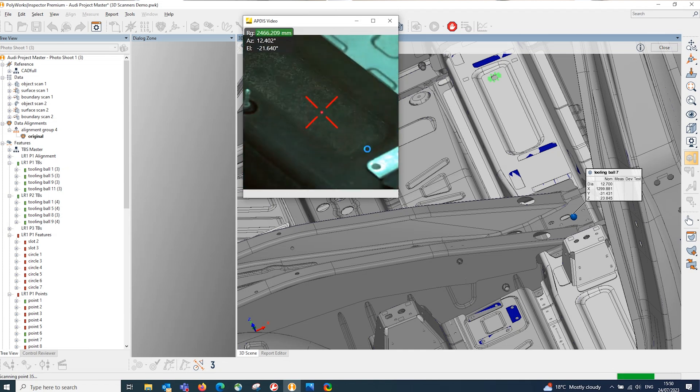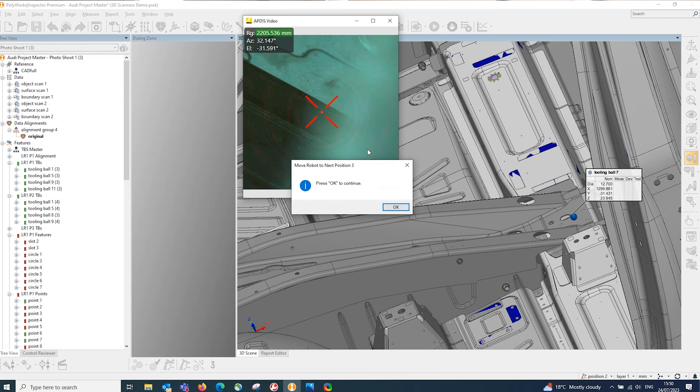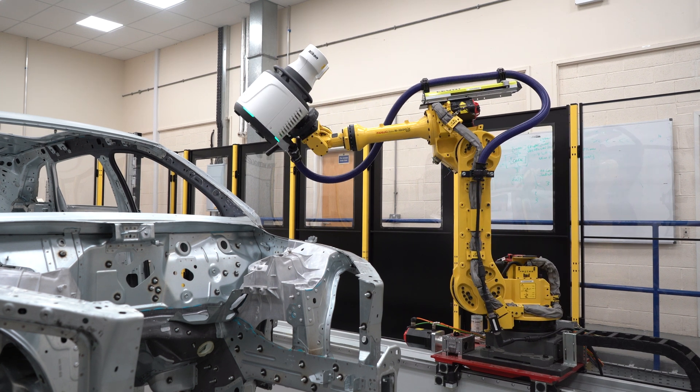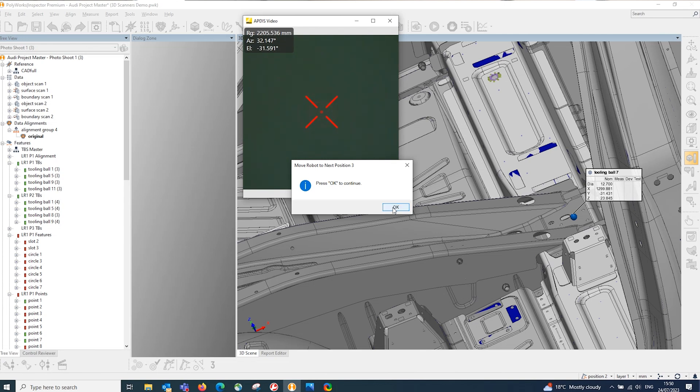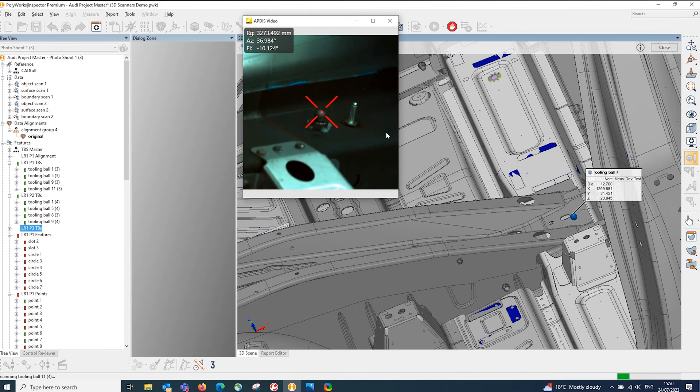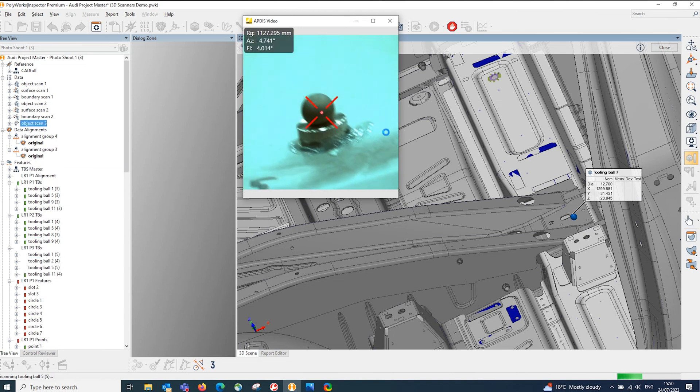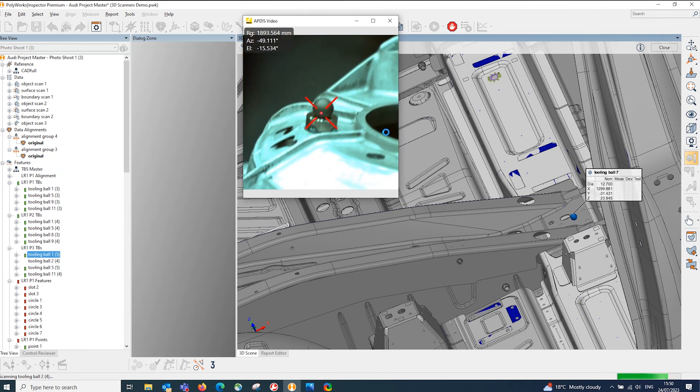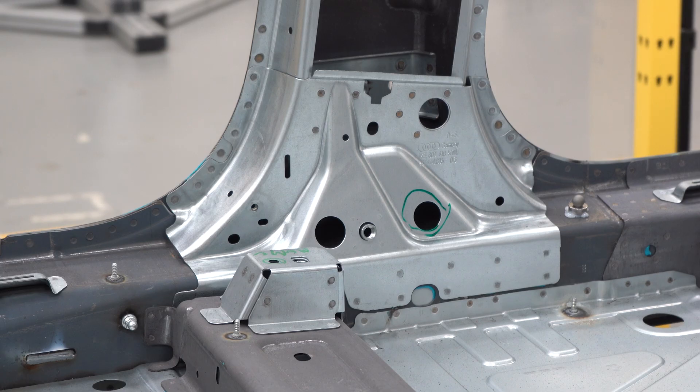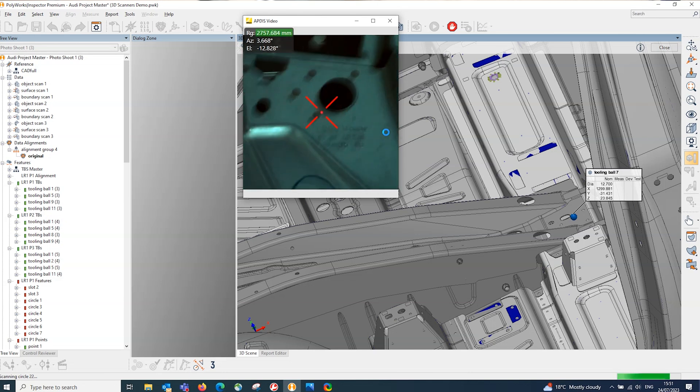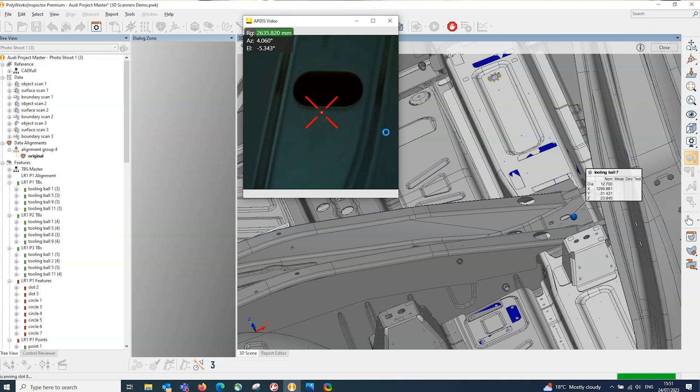In terms of maintaining these systems, obviously just like any other measurement device you want to keep them clean - I'm assuming there are mirrors and lasers so keeping that clean. Is there maintenance? We would recommend an annual calibration for the system and you can also carry out your own checks as well. There are a number of different checks you can verify the system's working correctly with. We have service engineers who are able to carry out calibration either at one of our offices or on site at your customer site. Are there any checks or calibrations that customers can do themselves? Within the toolkit provided by Nikon you can carry out a number of verification tests that you could do before you start for the day to make sure that the system's working correctly.